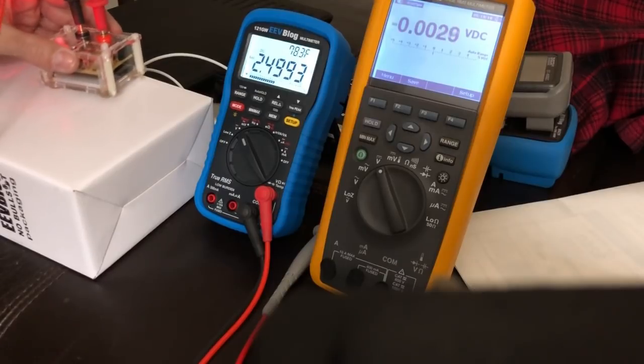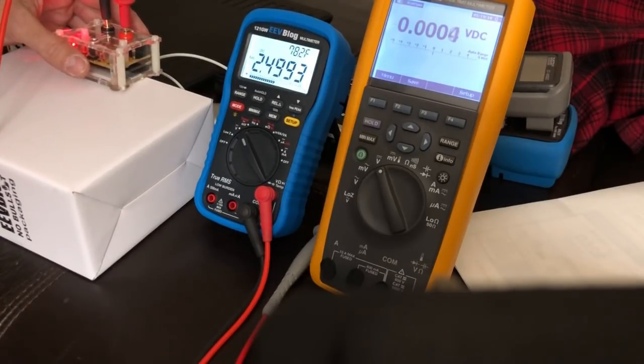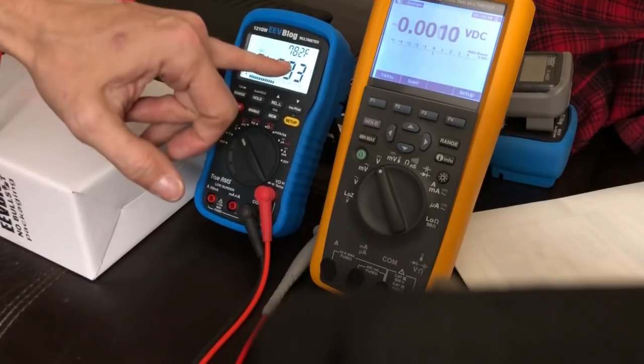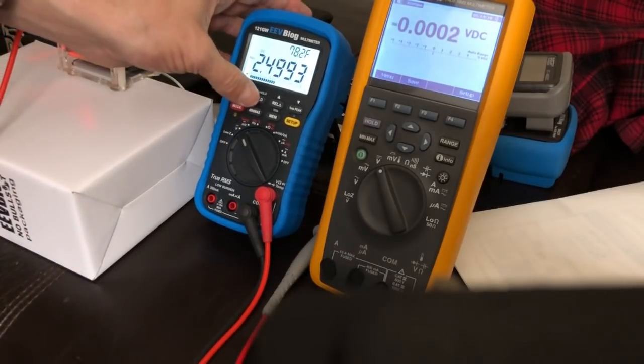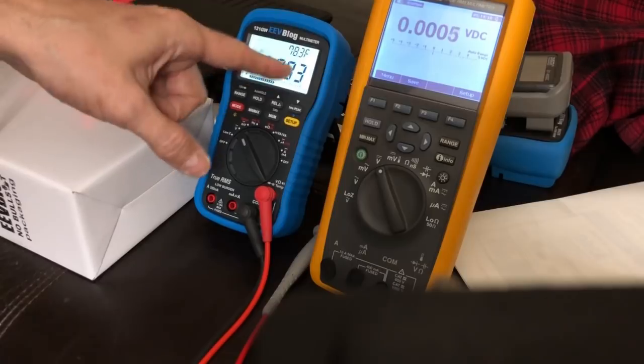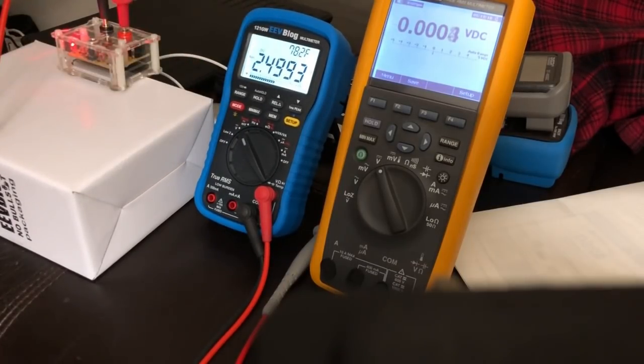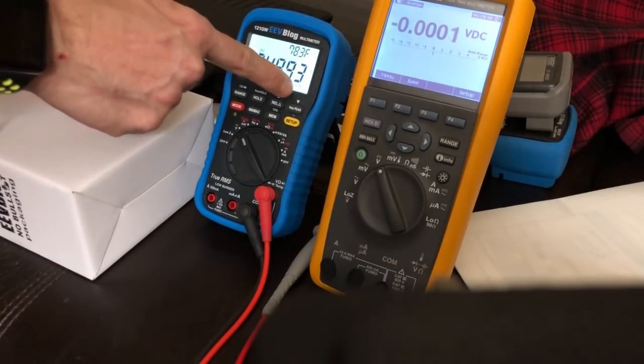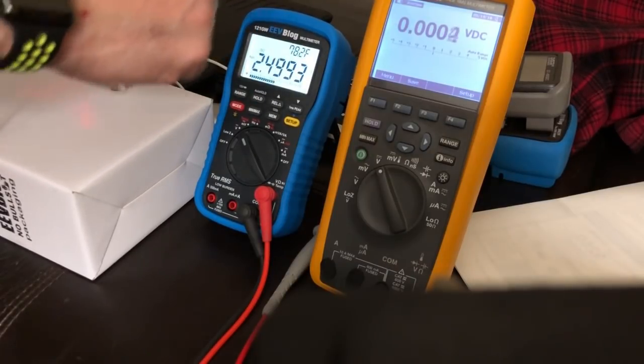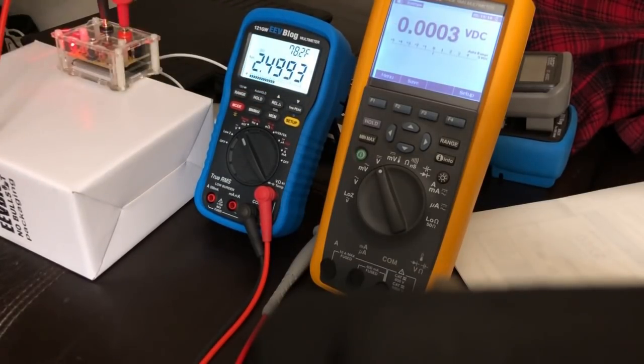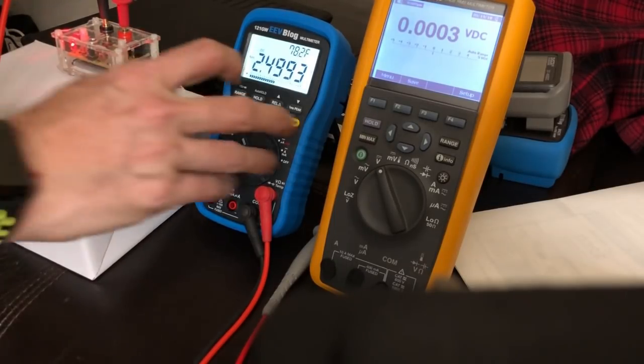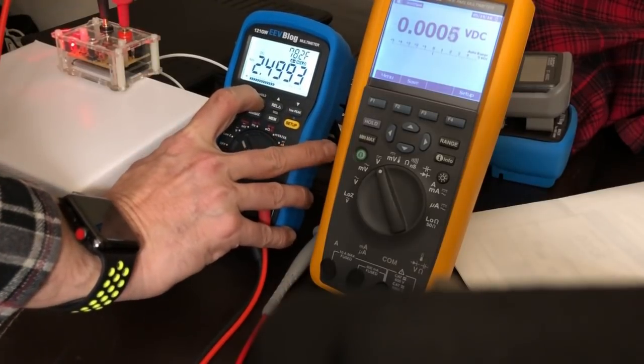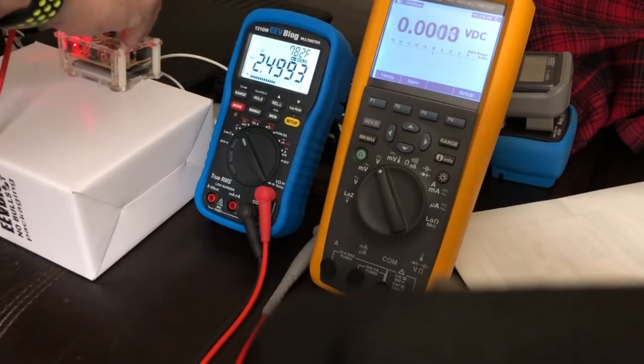So as I'm watching something, let's say the device under test is warming up and changing 1 microvolt at a time, I can actually see that reflected, and it will beep every time it gets to a different number. But not in the case of this meter - it has to be at least 40 microvolts difference between the last auto held number and the new number for it to actually register, calculate, and display. So if you think it may be slightly off for whatever reason, you just have to shut your auto hold off and forget about everything you were doing.